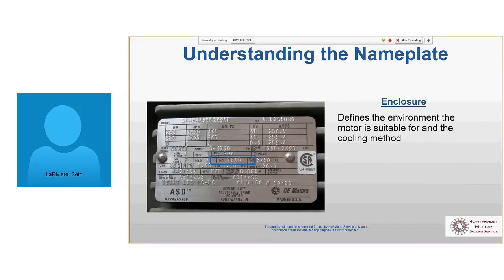In the enclosure, this one's TEAO, totally enclosed air over. So that motor's mounted in the airstream. Unlike this one, which has a fan on the back and a fan cover, this motor has no fan and no fan cover, and it is only going to cool by being mounted in a plenum where air's going over it. If it's not in that situation, the motor's overheating.